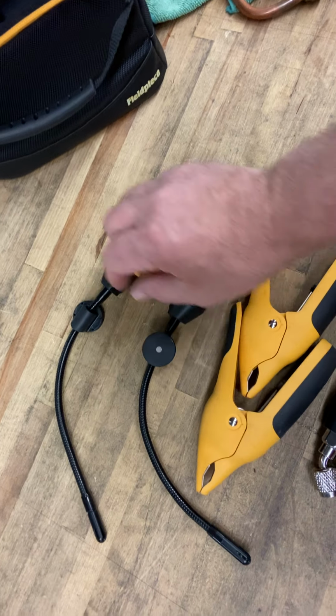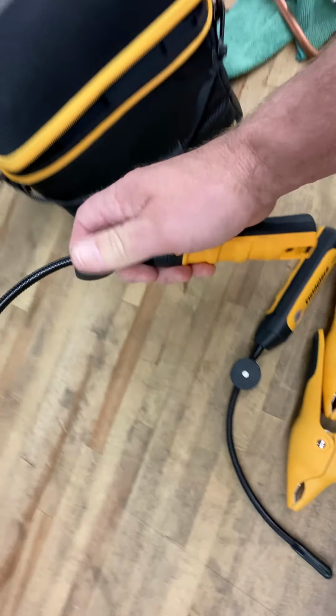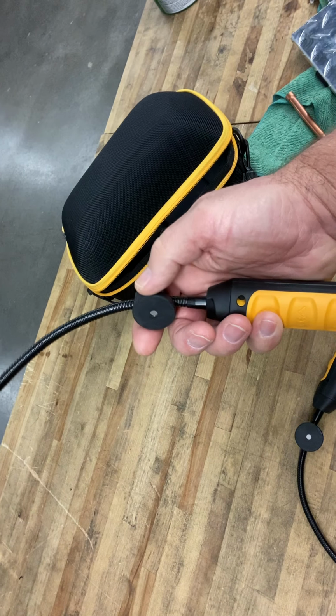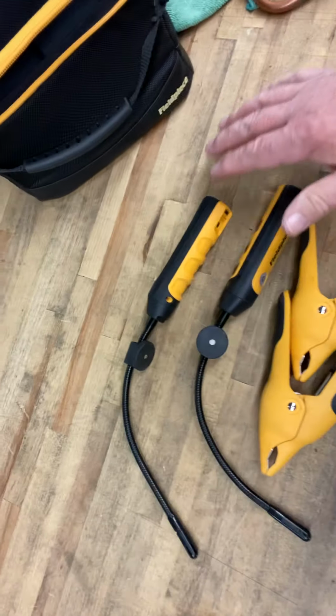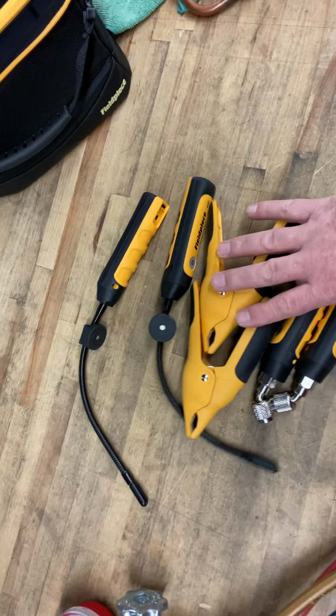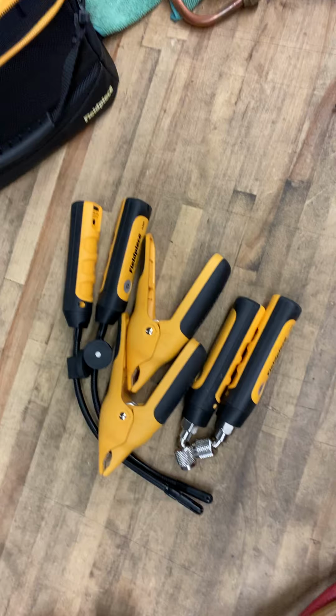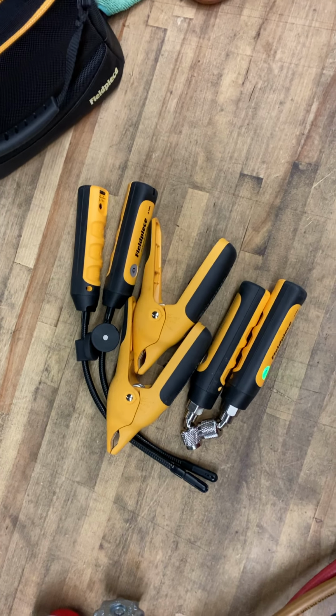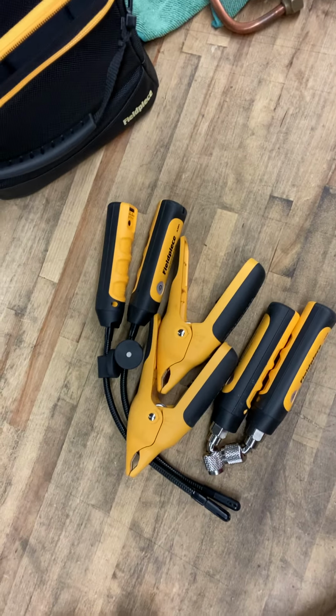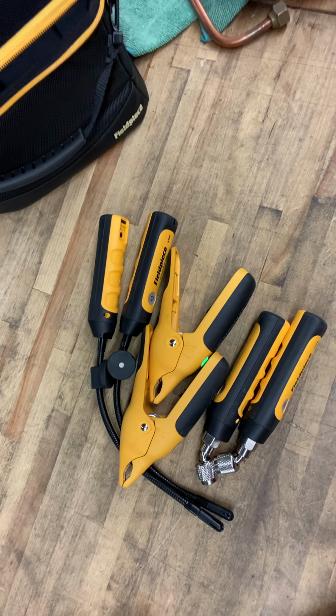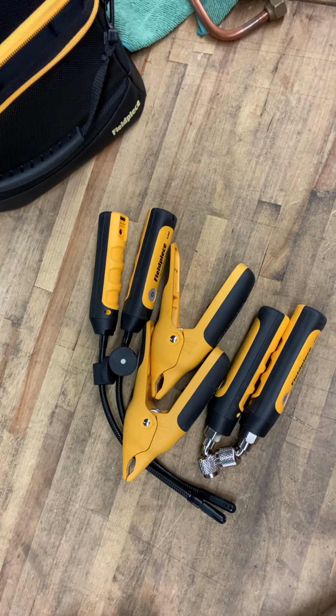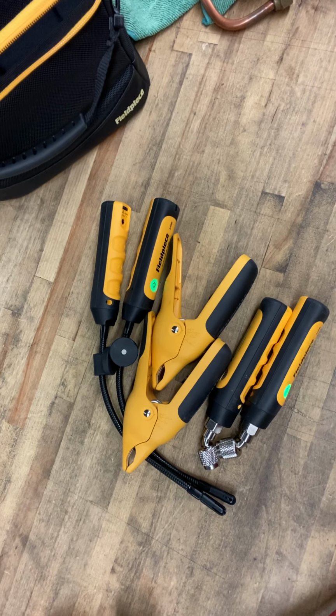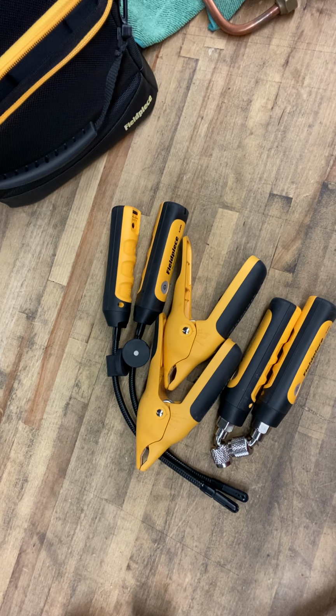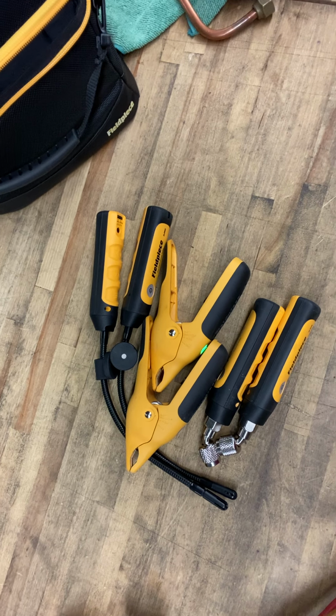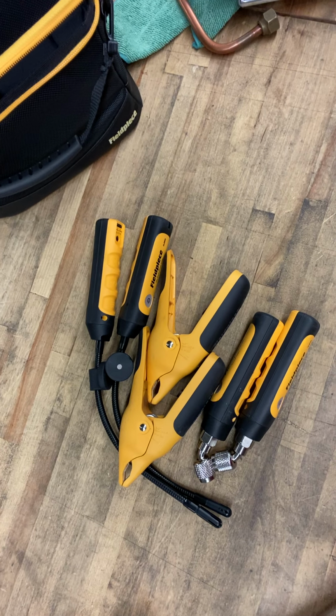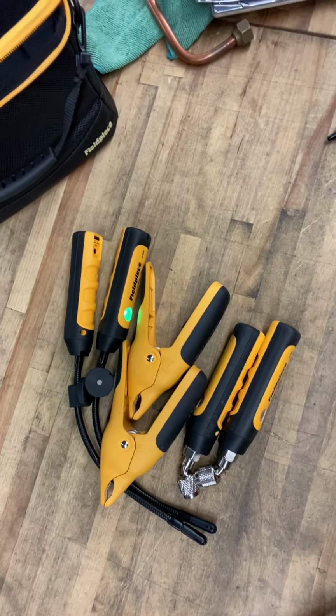I do have some magnets here, so if you're hanging it off a piece of ductwork up in the air, the magnet will keep it in place. Once you connect these, this set will give you a tremendous amount of information on your phone. You'll get your high side pressure, low side pressure, high side line temperature, low side line temperature, supply air, return air, wet bulb, dry bulb. It'll calculate BTUs being absorbed in the evaporator coil, and it'll calculate your airflow across the evaporator coil. So, a tremendous amount of information, and more than that.